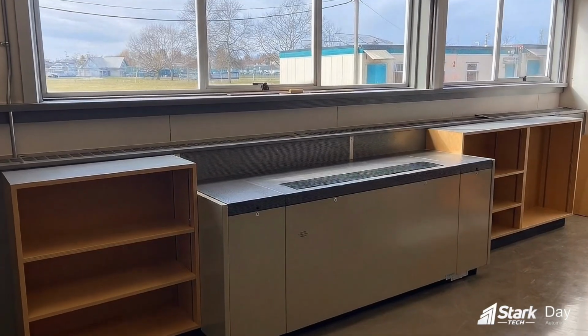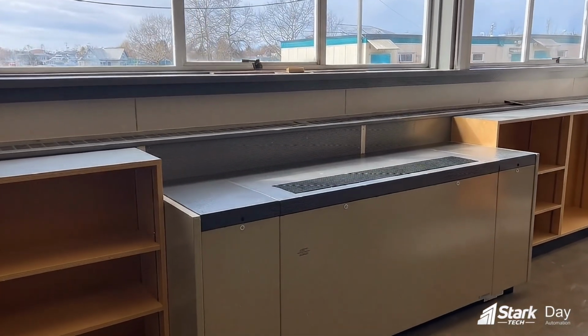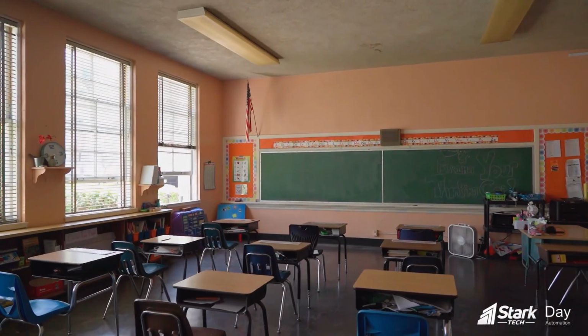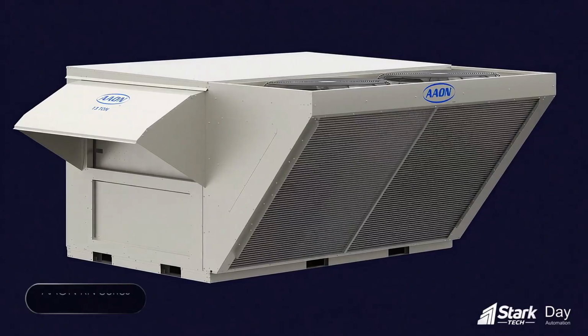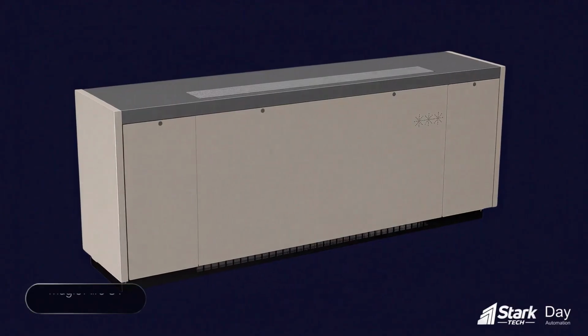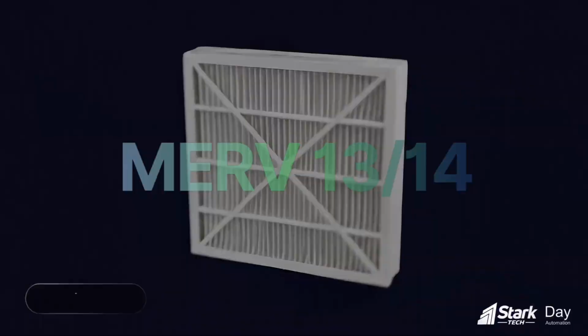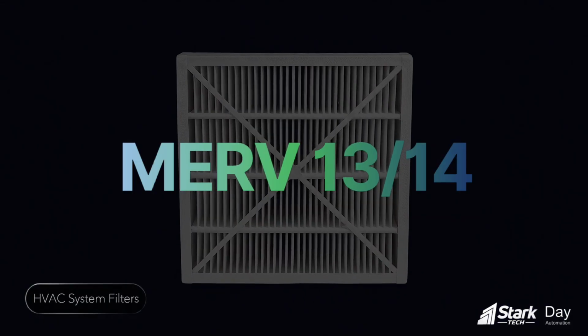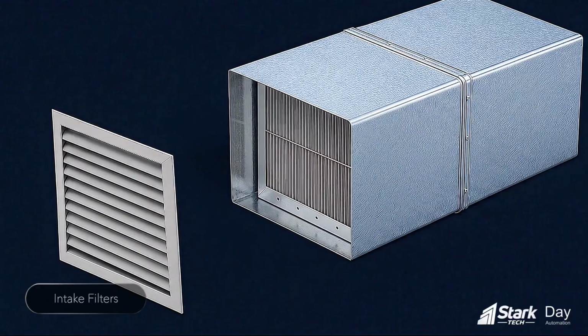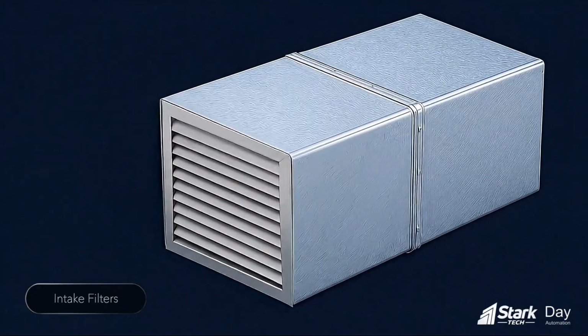We can engineer HVAC system designs that bring in more outside air to increase the number of air changes per hour. We can switch out the HVAC filters in the rooftop air handling units and the classroom unit ventilators to MERV 13, MERV 14. We can add intake filters to the outdoor air louvers to reduce pollen and debris load. And finally, we have sensors to monitor your indoor air quality so that you always know your IAQ status.